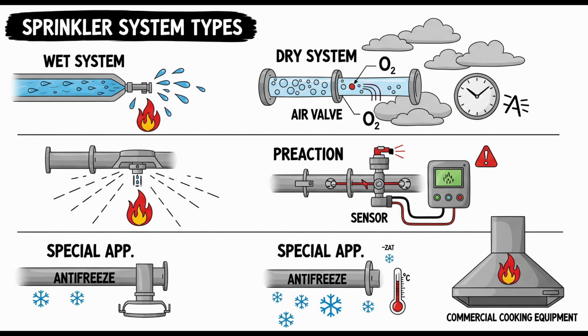Correct. The clock starts when the detector sees fire, and there's an absolute maximum permitted time of 3 minutes, regardless of the pipe length. That really emphasizes the role of the detection system in initiating the response quickly over potentially very long distances on a pier.